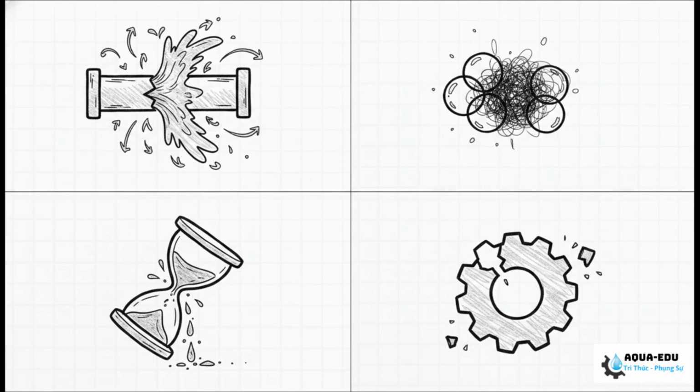Number 2, you've got particulate or organic fouling that is literally gluing the beads together and throwing off their natural density. Number 3, the backwash just didn't run long enough. Or number 4, you've got an internal mechanical failure, like a broken distribution nozzle that's creating dead spots. Listen, if those resins don't separate, your hydrochloric acid and sodium hydroxide are going to neutralize the exact wrong beads, rendering the entire regeneration completely useless.